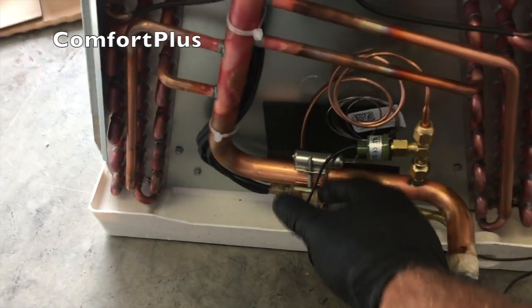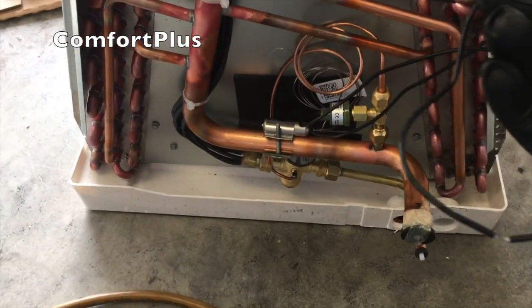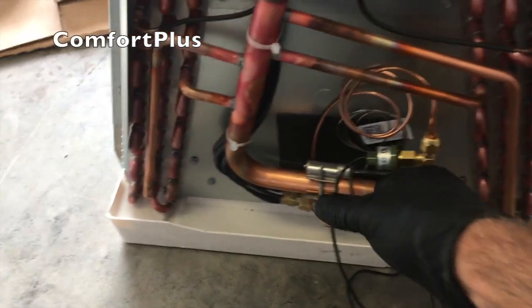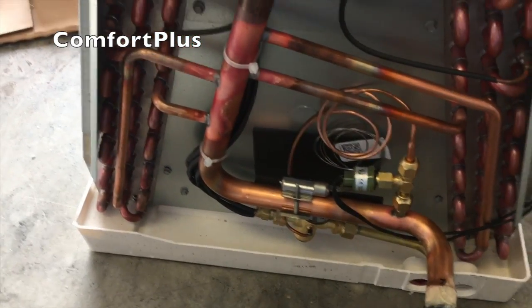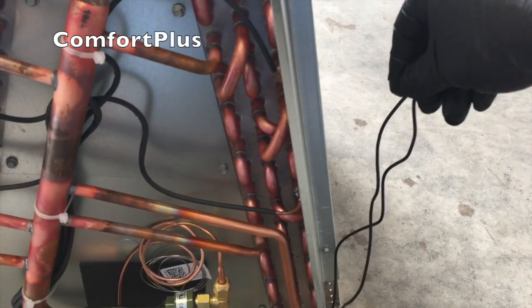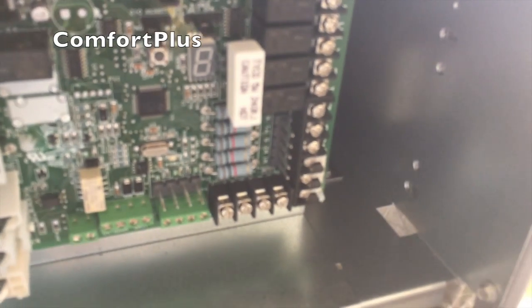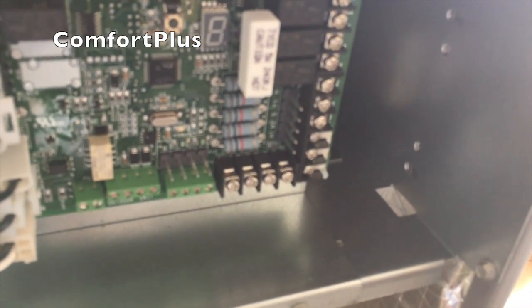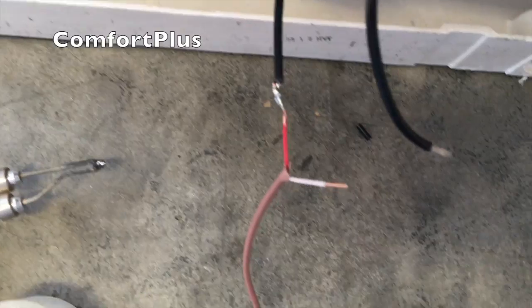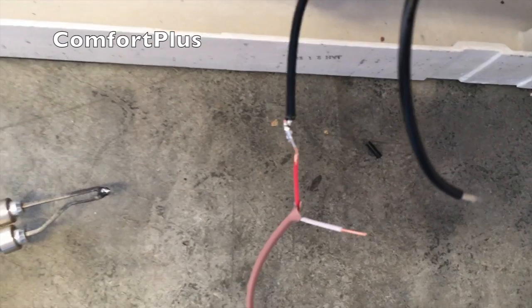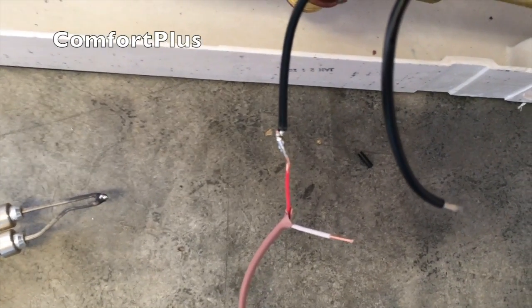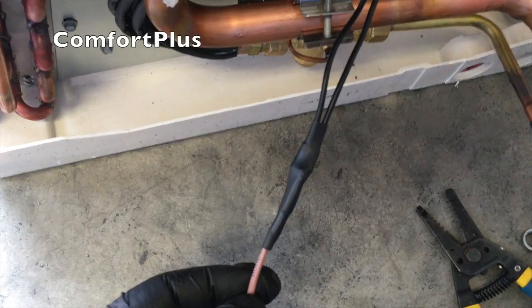I will extend these wires. I'll probably go ahead and maybe solder a piece on them, but I will bring them around and up the edge of the air handler on the inside up into the control box, probably through this hole here where I can make my connection to the thermostat wire going to the zone panel. Okay, I'm going to use a little solder and some heat shrink pieces to make this connection inside the unit, and it'll be good as factory. And there we have it.